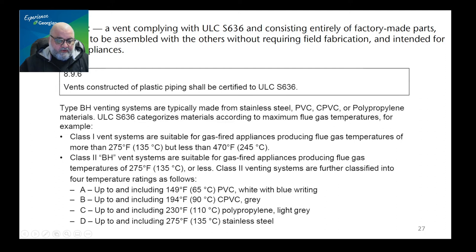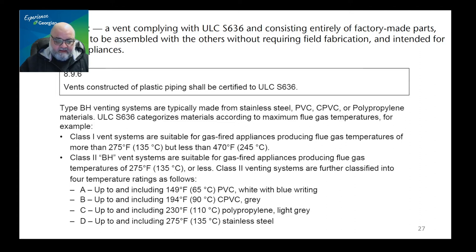In the codebook, you need to pay close attention to the type BH vent. It complies with ULC standard 636, and you must use parts manufactured by the same manufacturer — don't mix and match parts from different manufacturers. Also, clause 8.9.6 states that vent constructed of plastic piping shall be certified to ULC S636. And yes, that means all plastic piping.